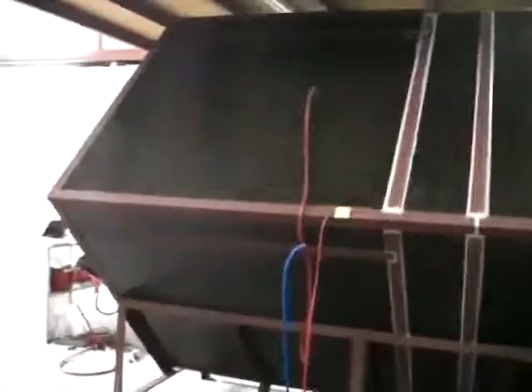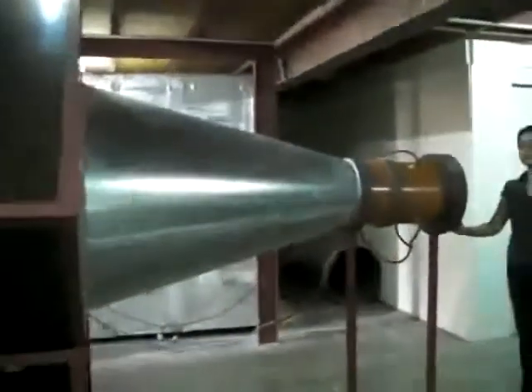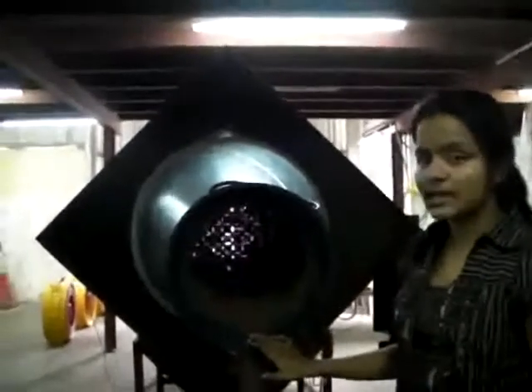Talking a little about the chamber construction. The size of this chamber is 1.4 into 1.4 into 2.4 meter. We have constructed a conical inlet nozzle of diameter 298 mm. The airflow straightener is also built as per BS 848. The conical transition from the conical inlet to the chamber is of diameter 300 mm, length 1.3 meter and diameter 1000 mm.